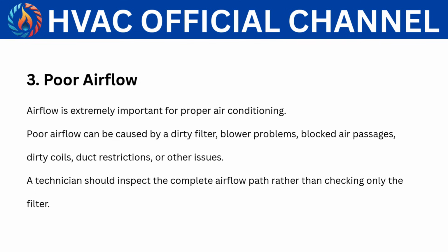3. Poor airflow. Airflow is extremely important for proper air conditioning. Poor airflow can be caused by a dirty filter, blower problems, blocked air passages, dirty coils, duct restrictions, or other issues. A technician should inspect the complete airflow path, rather than checking only the filter.